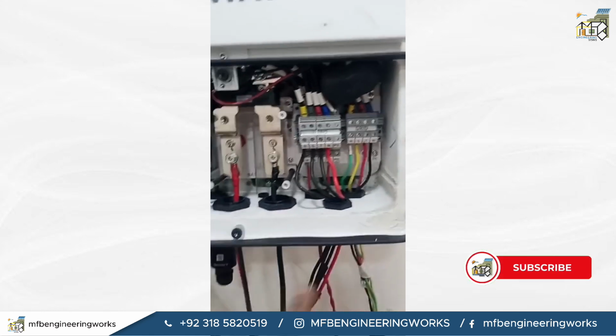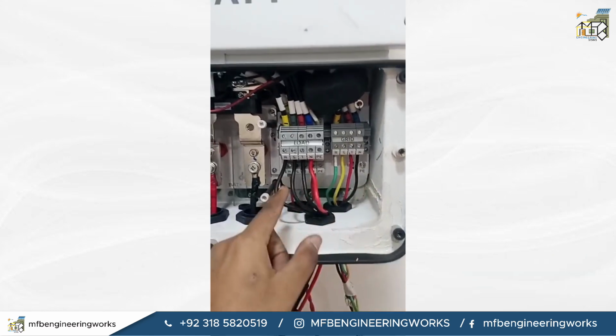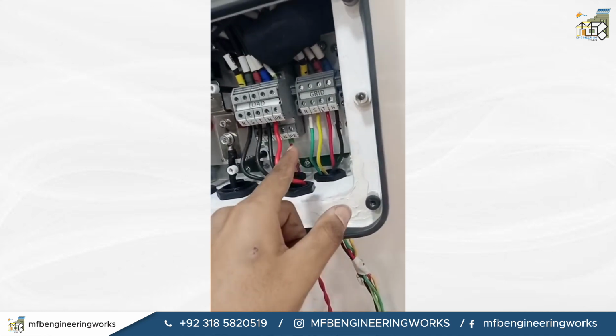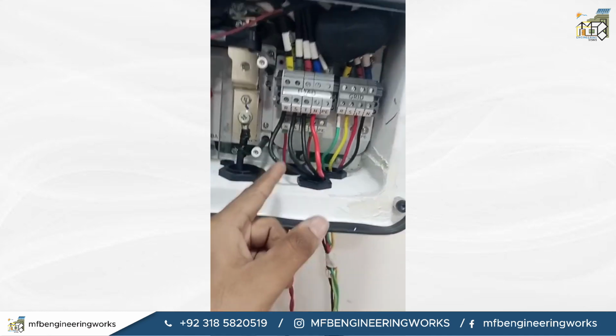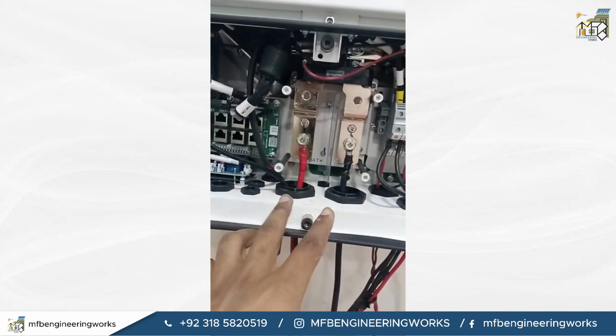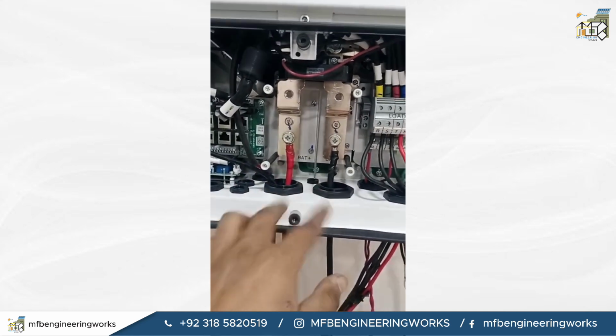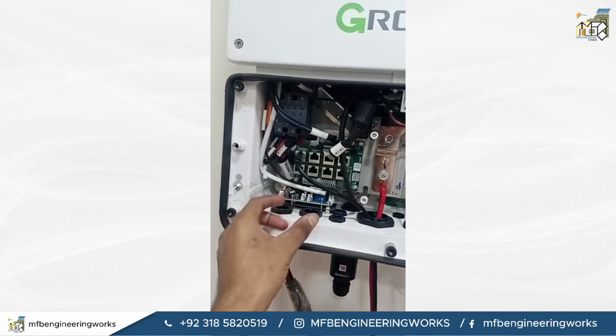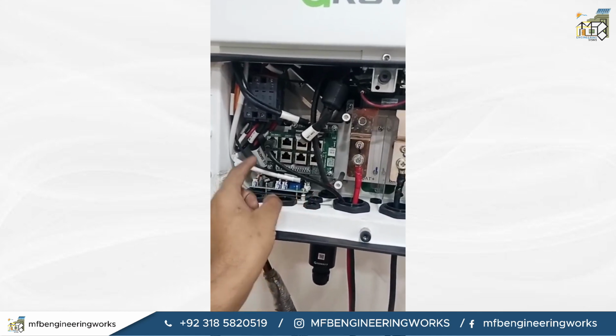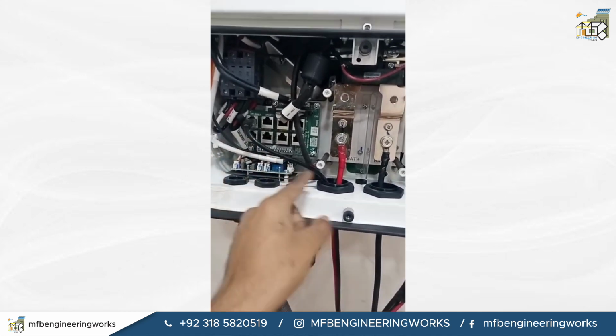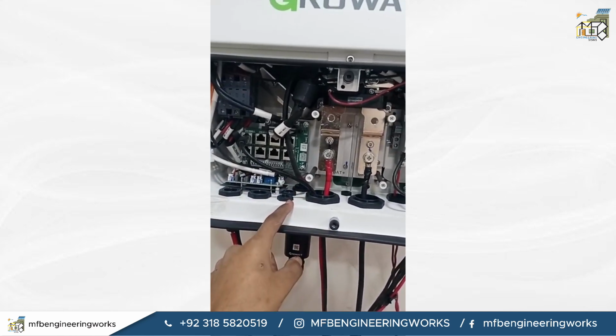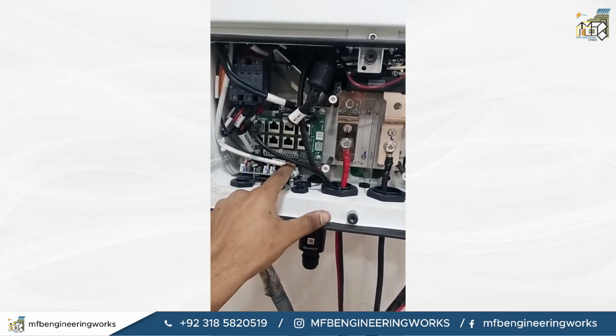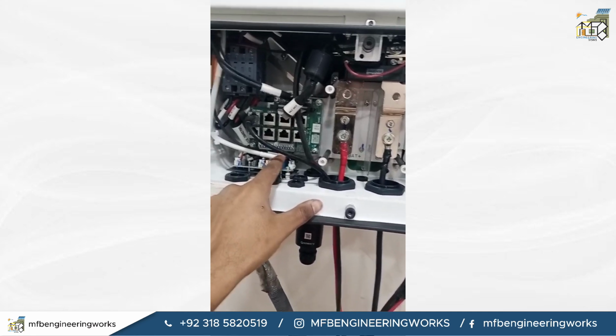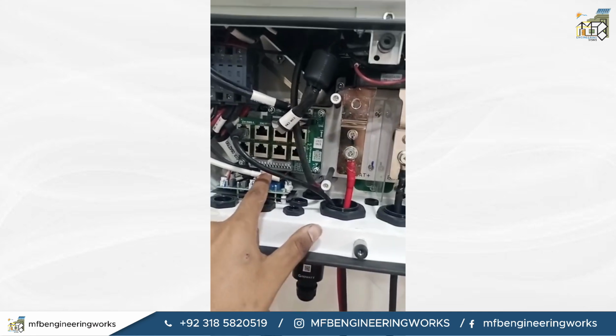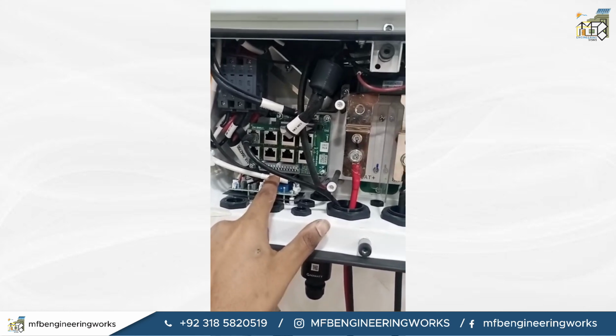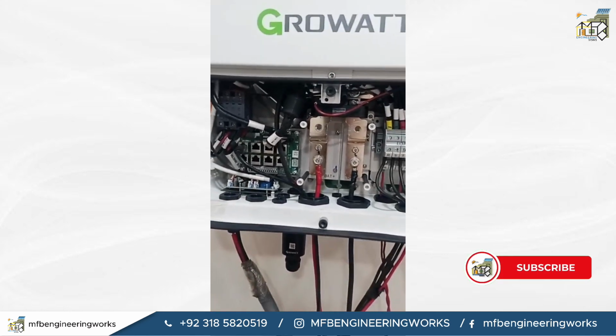Let me explain the ports. This is the grid port. This one is the load port. Behind that is the generator port, from where we can also get our smart load connection. These two points are for the battery — as you can see, we have connected the battery wires here — and this is the communication board for communication purposes, like where we have connected the BMS cable. We can connect the CTs in case we are using it as a zero export load; the CT points will be connected here, as you can see. We can also connect the genset DG controller pins here to synchronize the generator with this inverter.